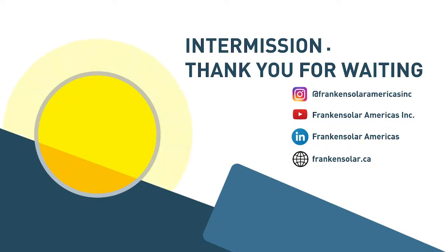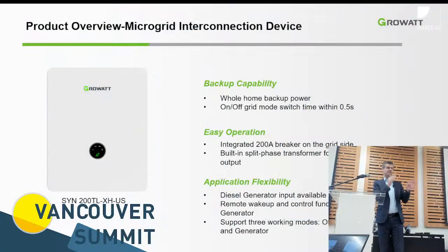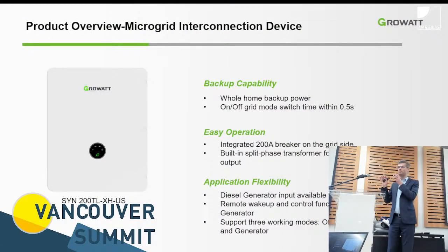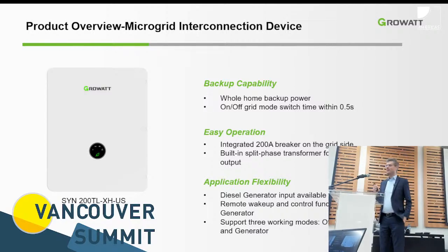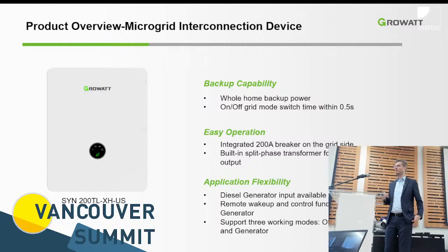It supports multiple modes. The focus, I'd say, is typically on-grid, because most of those hybrid systems are designed primarily as grid-tied systems with a temporary backup function, versus an off-grid inverter which is designed from a different perspective. It's typically always off-grid with a temporary function of a backup generator to recharge and get you over a few days of bad weather. In this case, the off-grid inverter needs to provide more peak power, because all the loads and all the starts need to come from that inverter, versus a normal grid-tie inverter that is more transformerless.